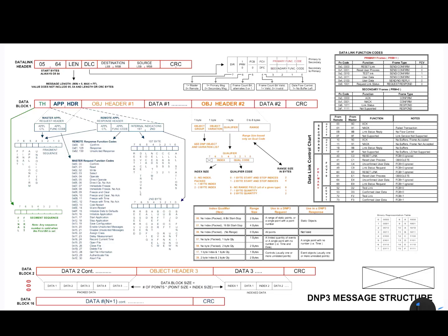So when we're talking about that DataLink control byte, that's the 1-byte value that takes up the fourth box, or the fourth position, if you will, in the DataLink header. And in order to interpret it bit by bit, on your breakout sheet, you can simply follow over to this breakout piece, or this guide here, that's going to look at each and every bit within that DataLink control byte to determine things like the direction bit, the first one.